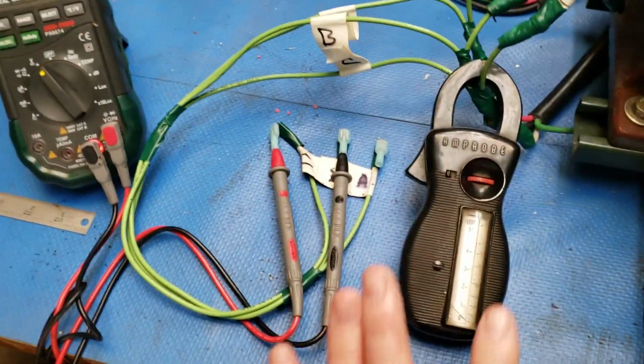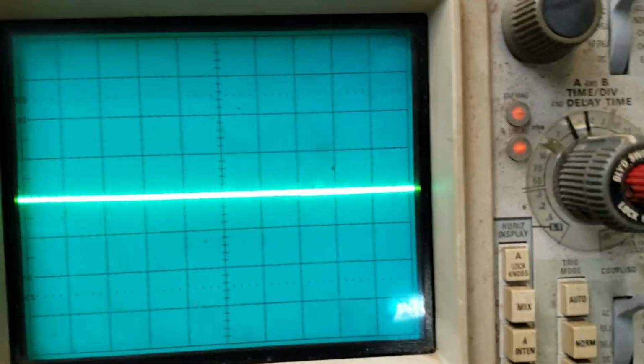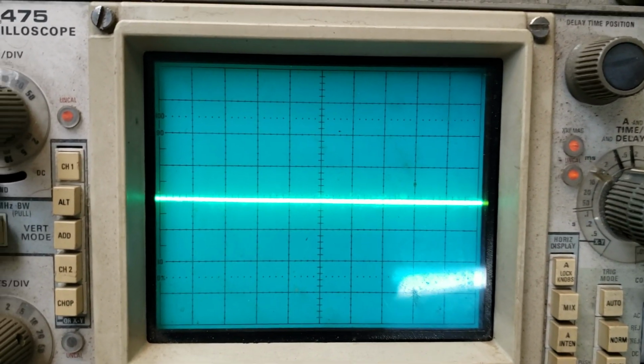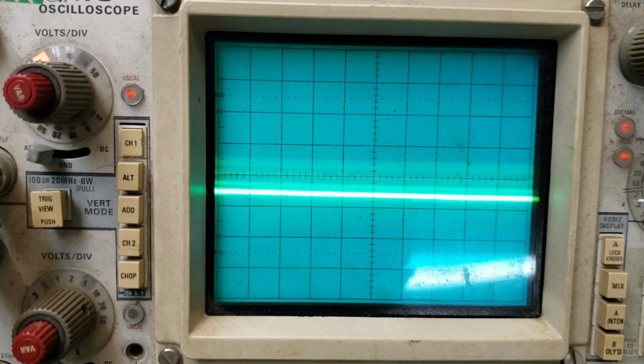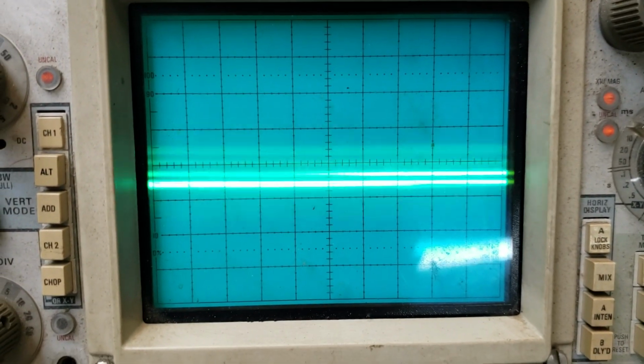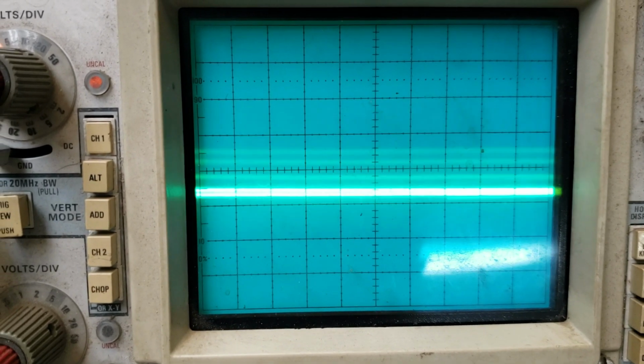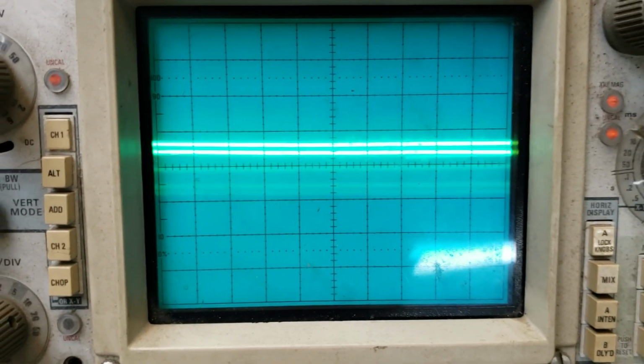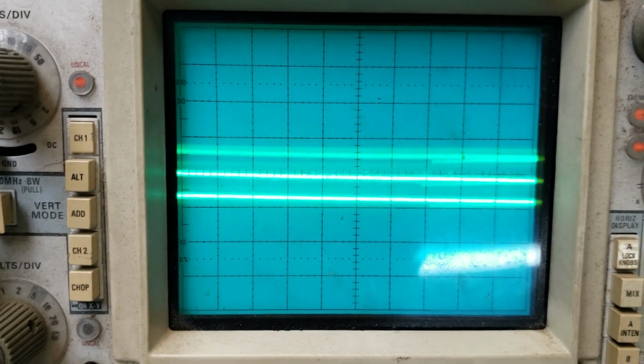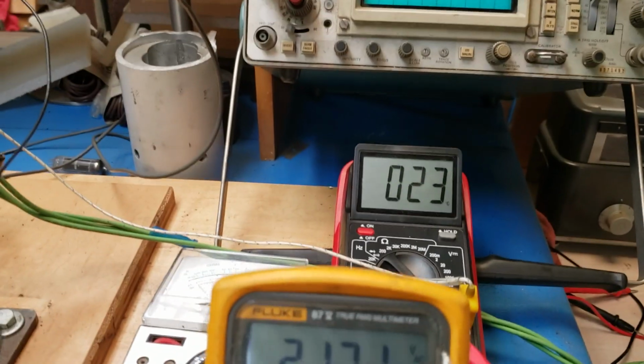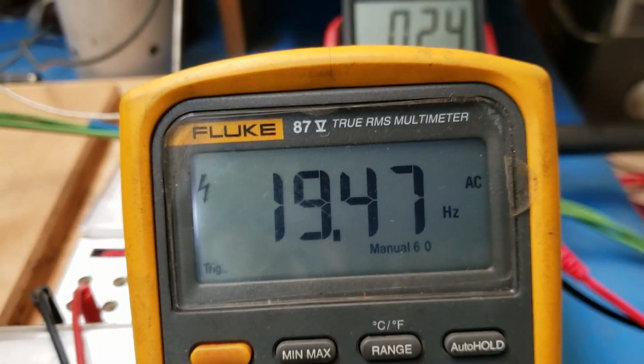We're at 0 hertz through the drive. Millivolts, hertz, drive, input amperage, output amperage, heat soaks. No load, cold start. We're just going to pay attention to the oscilloscope. We're coming to 10 hertz. 21 volts, frequency 19, perfect power. Let's check that.